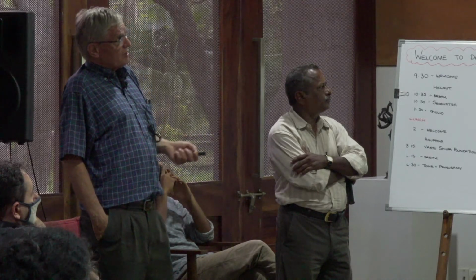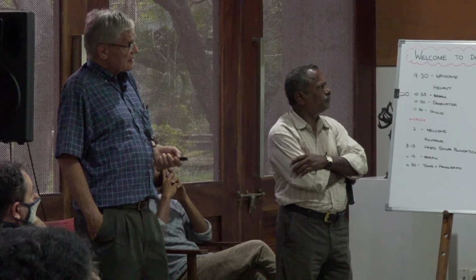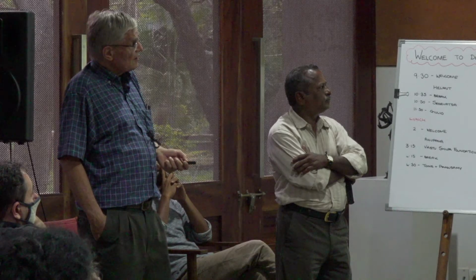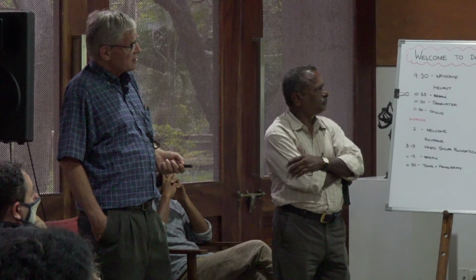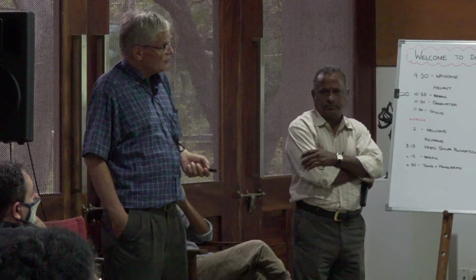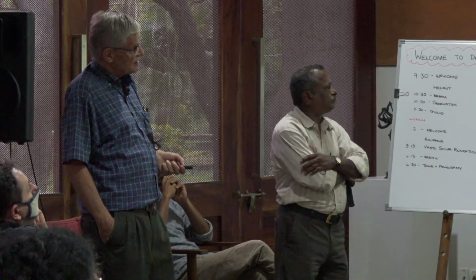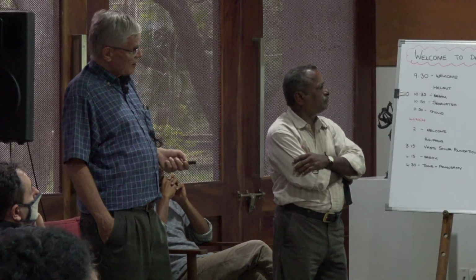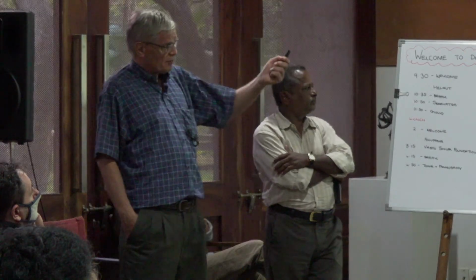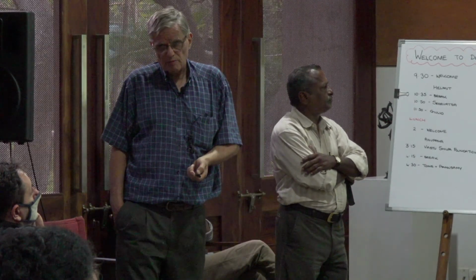So it has an HT plan, an LT plan, a road and street lighting plan, and it has phasing. The phasing is, of course, taken from the master plan of Auroville: 5, 15, 25, and 50. It comes to basically a distribution capacity of almost 1 kilowatt per person.